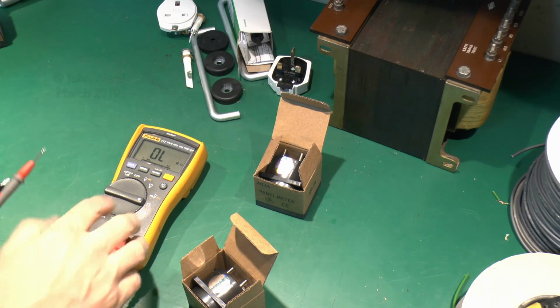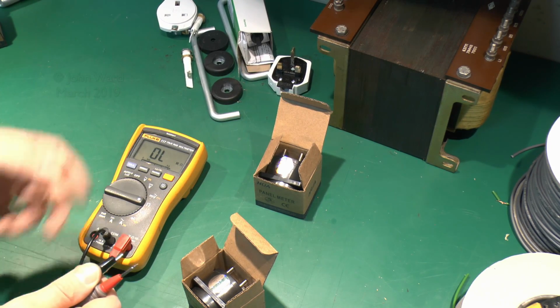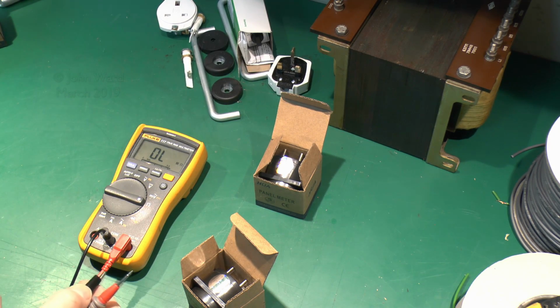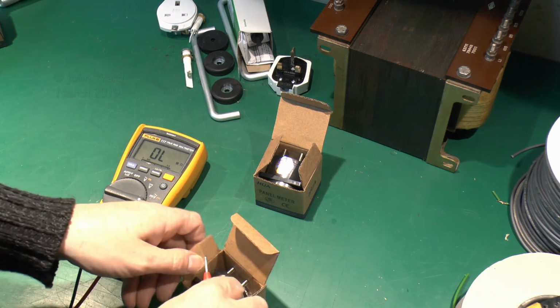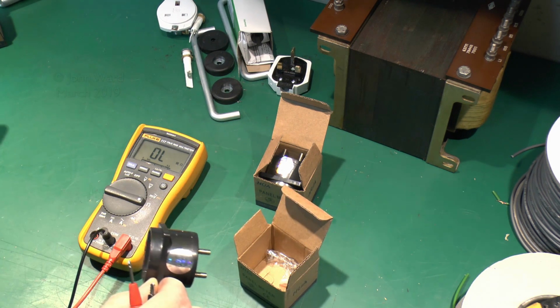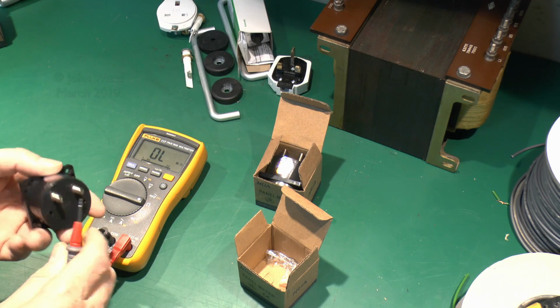Modern meters, if you put them in voltage mode, have about a 10 mega ohm impedance on the input. This one's got about 2 or 3, but that's still plenty high enough. Also bear in mind that's at DC, so at AC it may well be somewhat different.